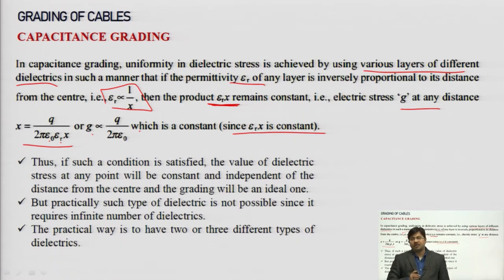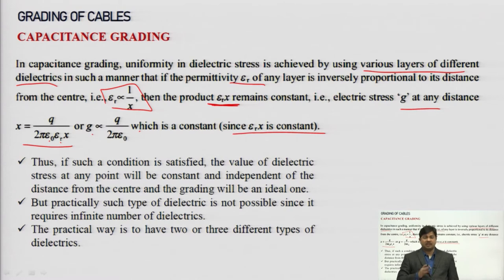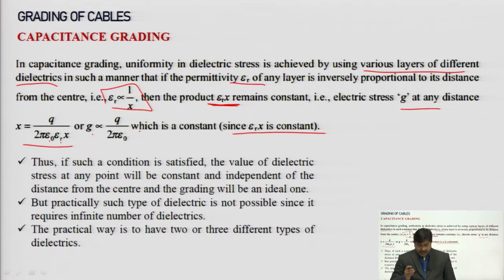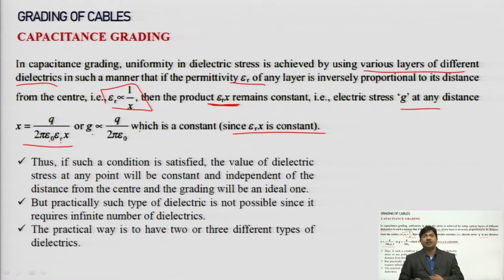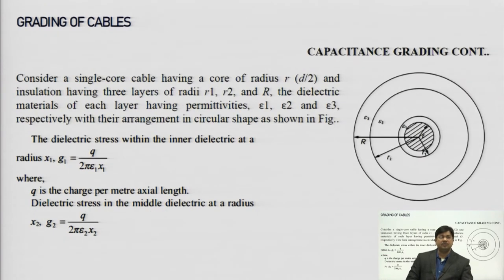But practically, this method is not easy to implement because we need multiple types of dielectric material, and we must ensure that all insulating materials have almost the same dielectric strength, the same thermal coefficient (temperature-bearing capacity), and sufficiently high mechanical strength. Ensuring all these properties match across a variety of insulating materials is complex. That is why practically only 2 or 3 different types of dielectric are used.